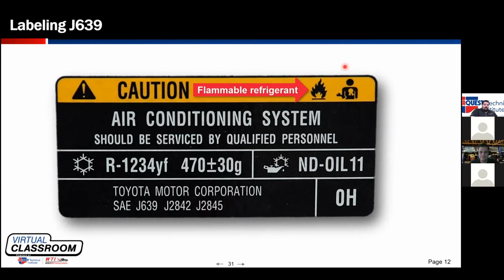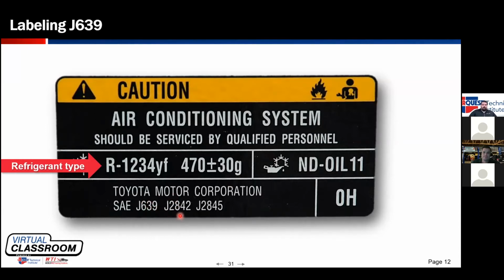We have a notice that we have a mildly flammable refrigerant, hence the fire. We're told our charge capacity and what refrigerant oil. Now, this is a Toyota label. Toyota is nice enough to tell us on the label exactly what oil goes in the vehicle. Some manufacturers just say PAG oil, and you have to go to the service manual and try to figure out what the correct oil is. Toyota is nice enough here to tell us that this vehicle gets ND11 as its oil. Refrigerant type 1234YF, 470 grams plus or minus 30. So we have a charge specification and a tolerance. It's a Toyota vehicle. We're claiming that this vehicle system complies to J639, and also that we have a 2842 evaporator core installed.